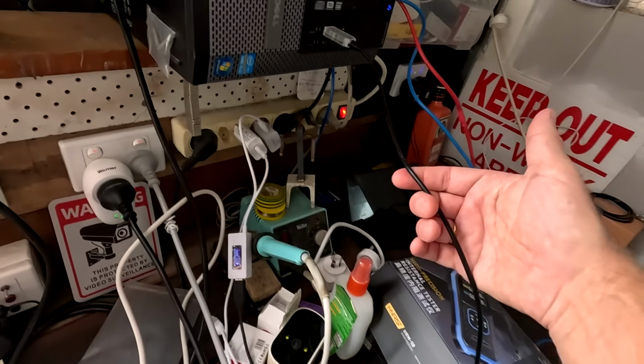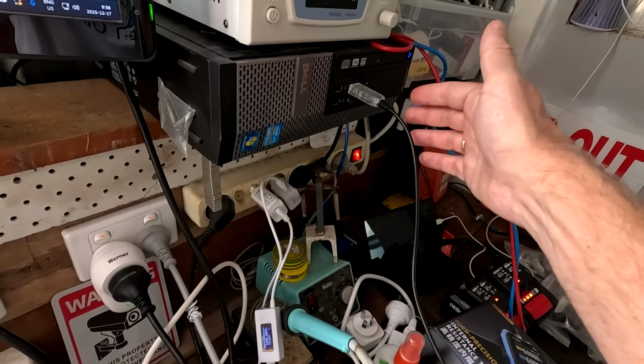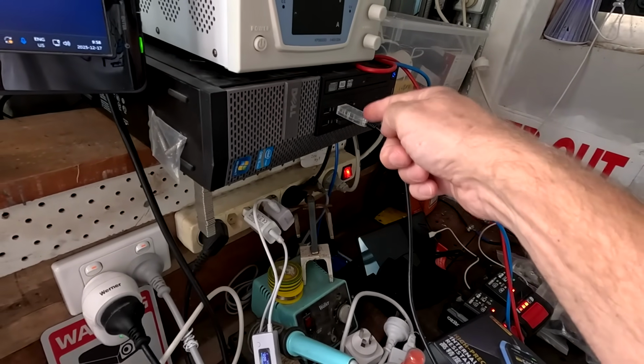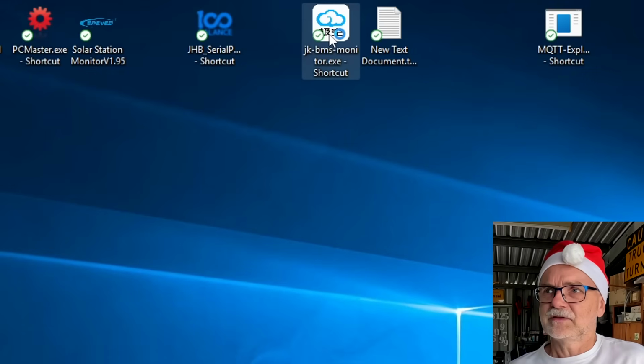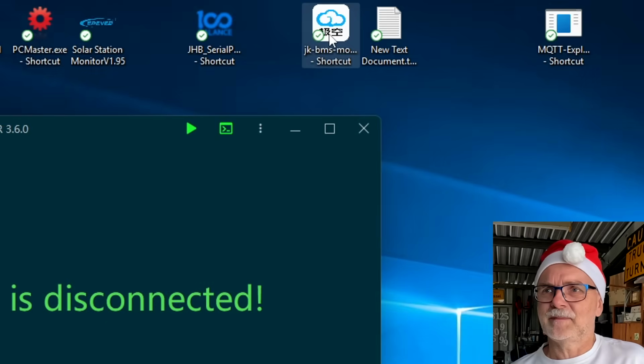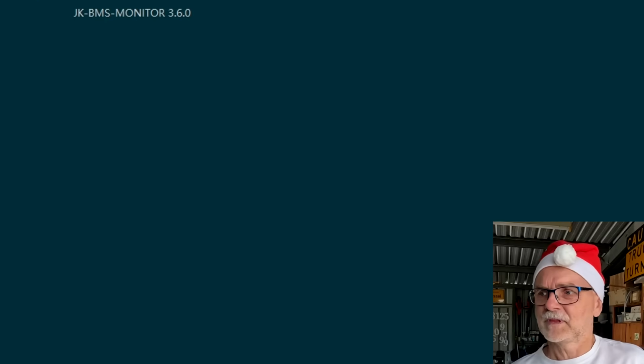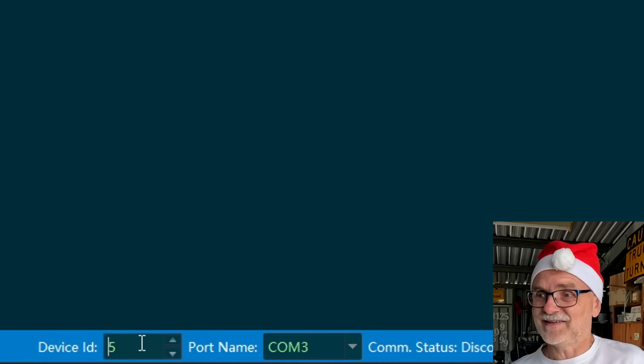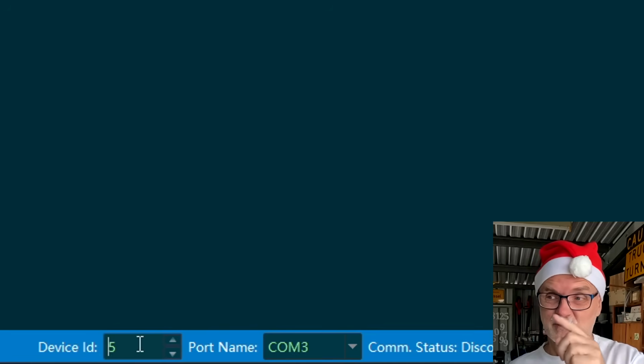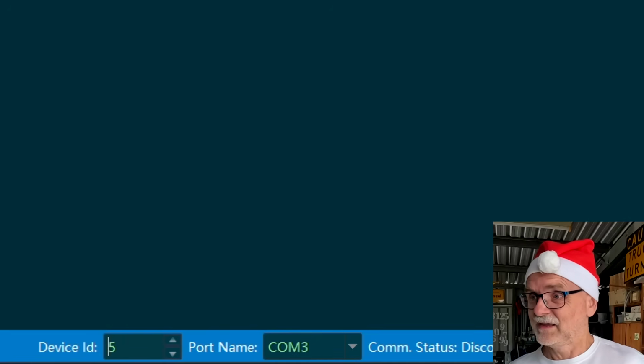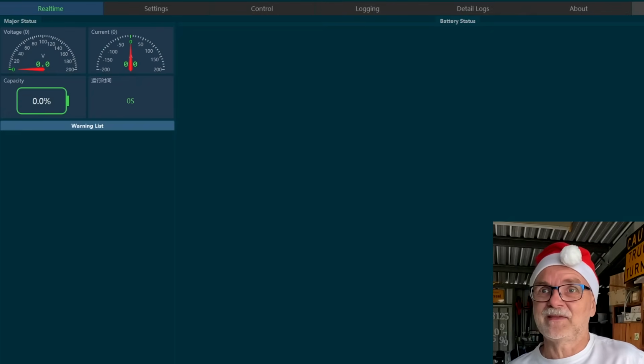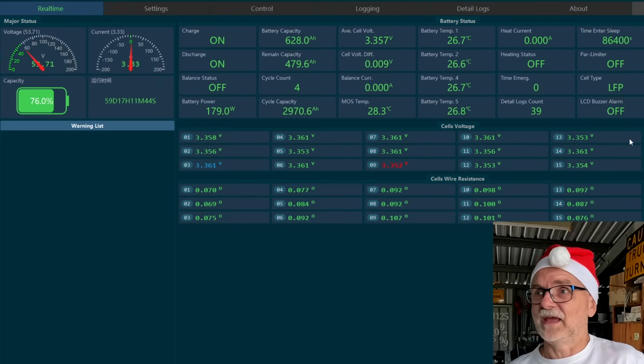And obviously this network cable plugs into an RS485 to USB adapter into your computer. Nothing new here. Okay, we then start the JK BMS monitor software. We set device ID 5 as per dip switches for this BMS and click on connect. And this should connect to the single BMS now. Yep, there we've got all the data, right?